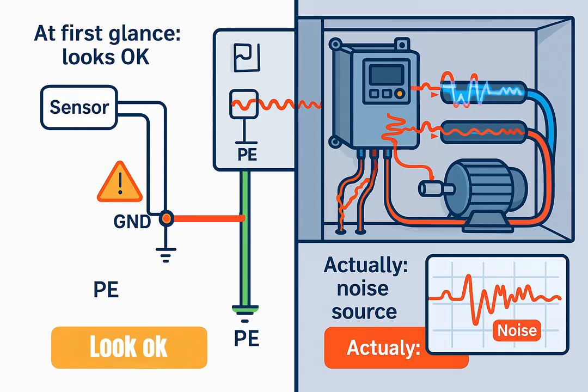Now imagine in the same panel, you have a VFD driving a pump, fan, or conveyor motor. The VFD generates high-frequency PWM waveforms at the three-phase output, with leakage currents through the motor frame, power cables, and parasitic capacitances. All of this high-frequency noise eventually finds a way back to the source, and a significant part of it returns through the PE bar. If your analog sensor GND is tied to PE, then that high-frequency noise is now riding on your signal ground. The reference point of the PLC is no longer stable.